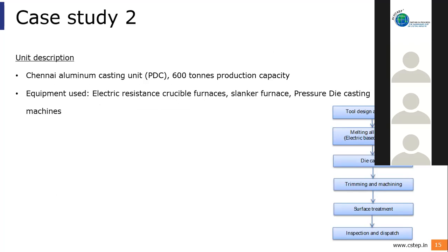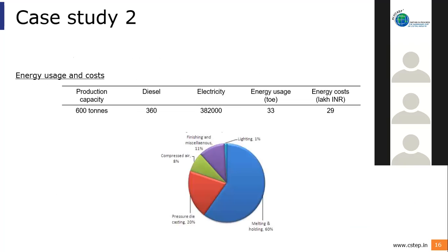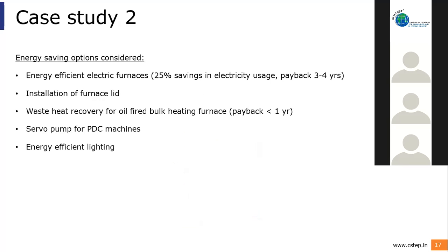This is another die casting unit, with a 600 ton annual production capacity. It has electrical furnaces. Next slide, please. The total energy cost of this particular unit: the diesel cost was 360, and about 3.8 lakhs of energy usage, in terms of 33 TOE, and the energy cost is about 29 lakhs per year. Next, please. And here, a saving potential of around 25% was identified, out of which around 15 to 20% was implemented and achieved in the unit.